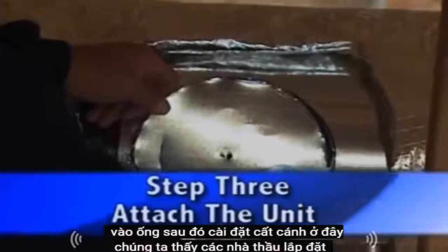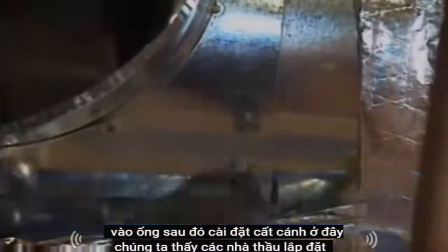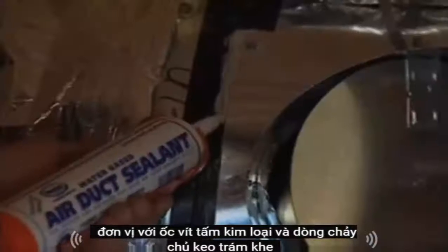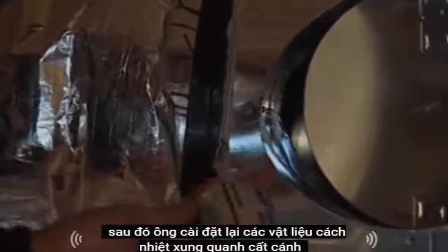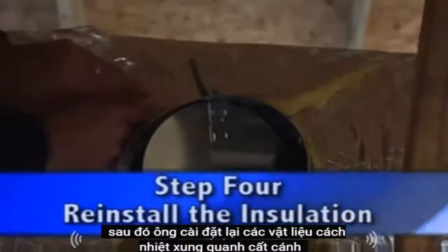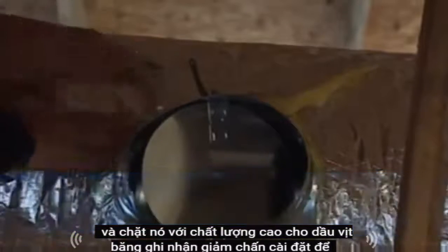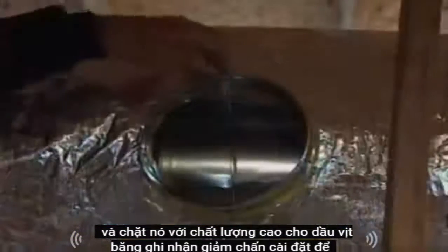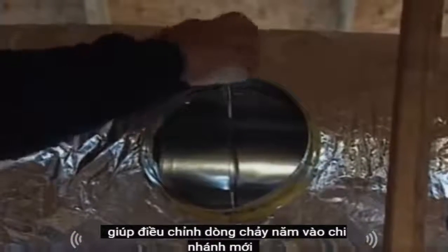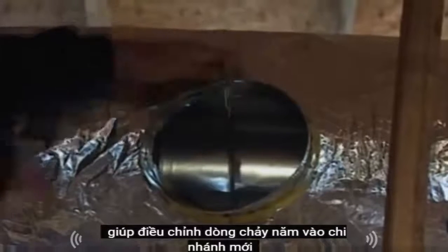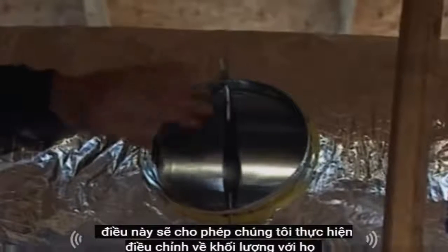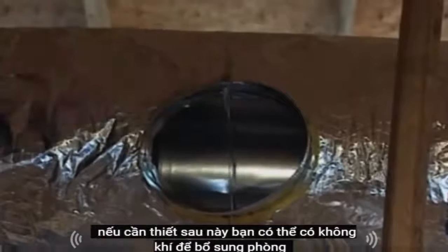Then install the takeoff. Here we see the contractor install the unit with sheet metal screws and master flow duct sealant. Before he installs the sealant, he pushes back the insulation. Then he reinstalls the insulation around the takeoff and secures it with high-quality foil duct tape. Note a damper is installed to help regulate the airflow into the new branch. This will allow us to make adjustments in the volume of air if needed later.